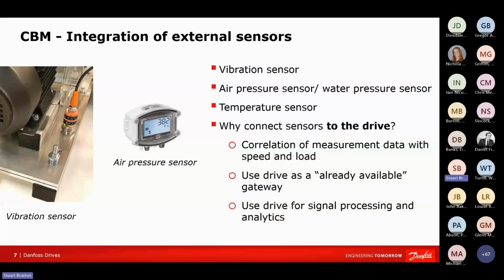Our second CBM feature is the integration of sensors to the drive. And I use the word sensor generally rather than just vibration sensors. Vibration sensors are the most common type of sensor to connect for some sort of condition-based monitoring, but we're not limited to vibration. Really, we can connect any type of sensor at all to the drive, as long as it is a 4 to 20 milliamp format. We don't really care what we're measuring.